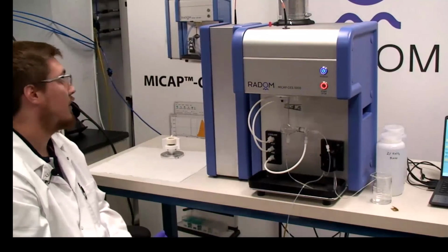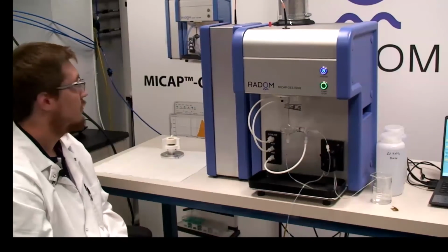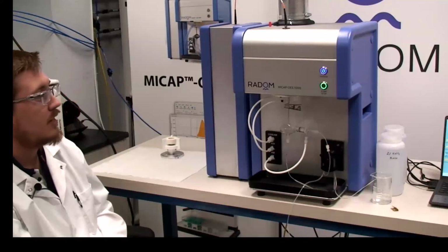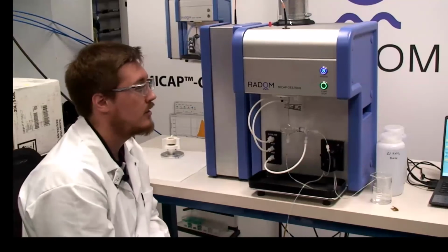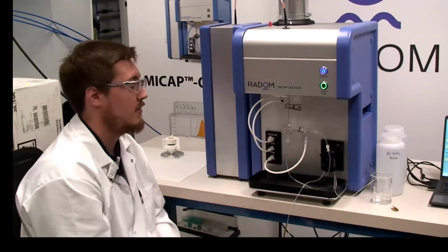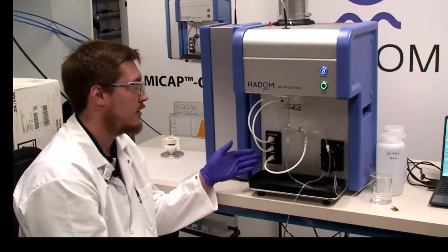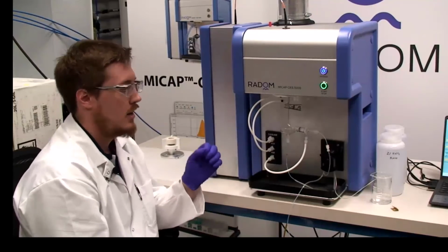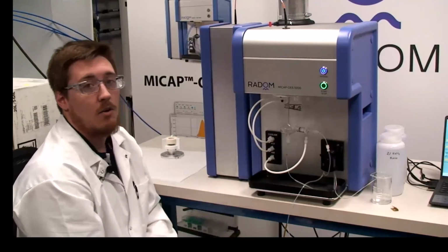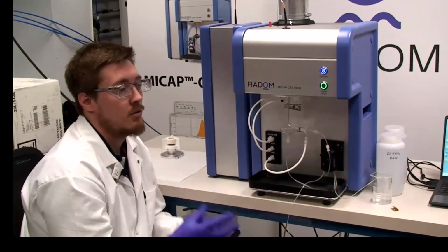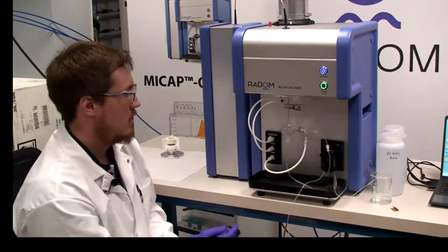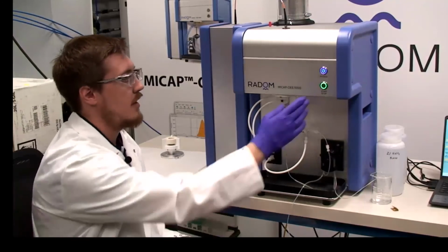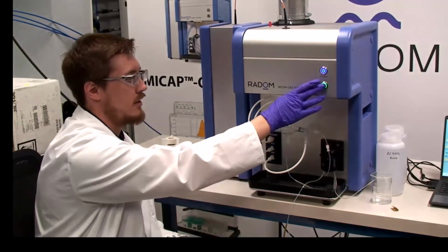So Jake, you hit the exhaust. So we have our exhaust on and our 3 gases, which are nitrogen, argon, and compressed air. The nitrogen will be running all the coolant, auxiliary, and nebulizer functions, and the argon is only used for the ignition, so a small tank of argon can last you years. So now that everything's set up and we have a green light, we're going to ignite the plasma.